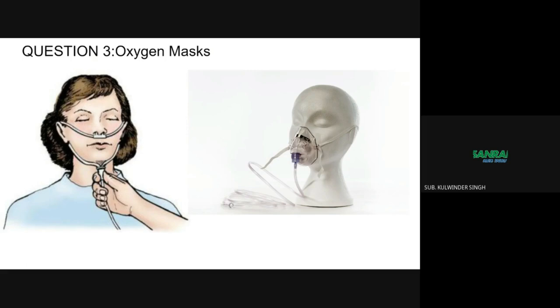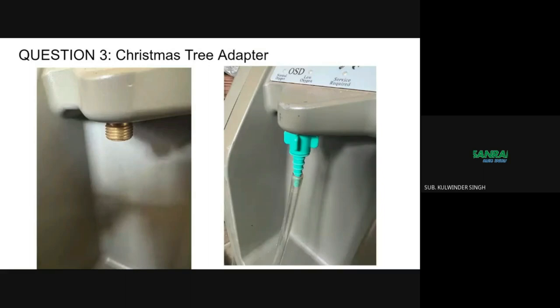The patient outlet tubing connector, also known as a Christmas tree adapter, connects the nasal cannula or face mask tubing to the concentrator outlet when a humidifier bottle is not used — for example, at low flow rates or when using a flow splitter. The Christmas tree adapter has a wide base with threads and is screwed onto the concentrator's patient outlet fitting to enable connection of oxygen delivery accessories.